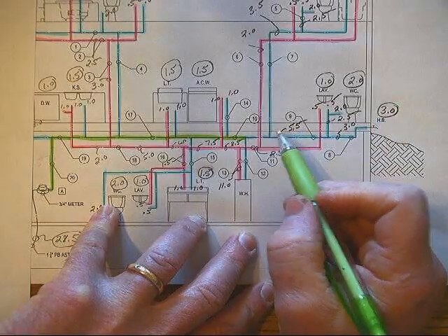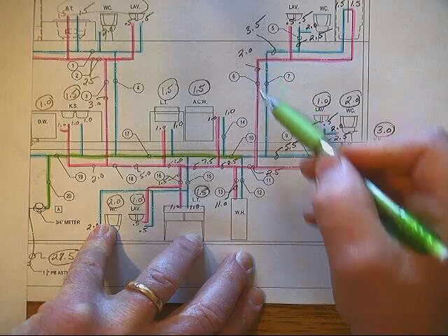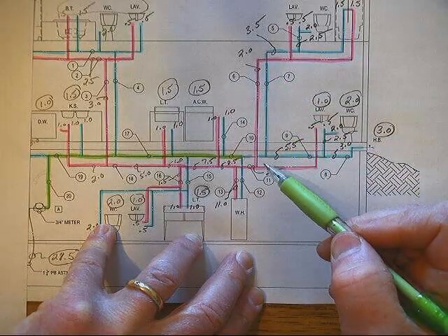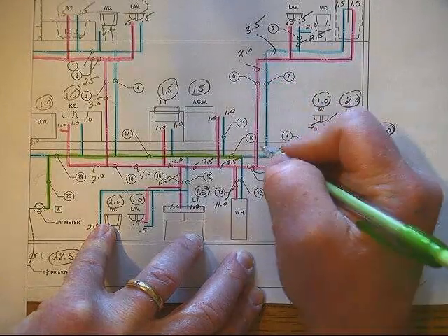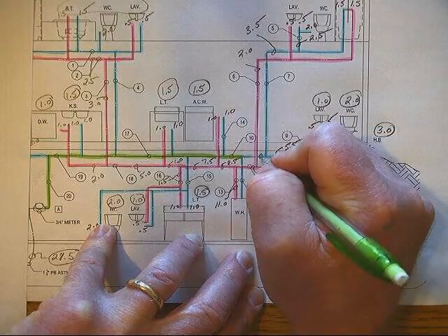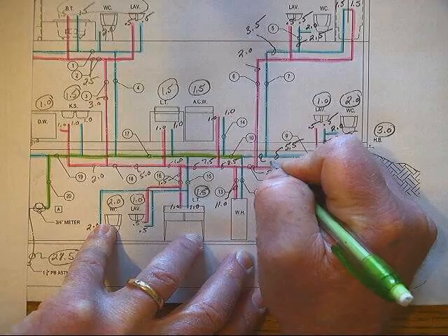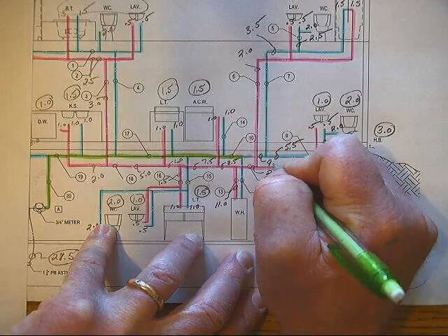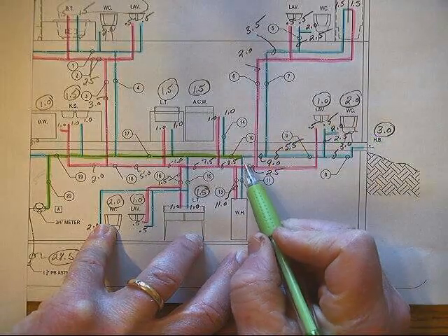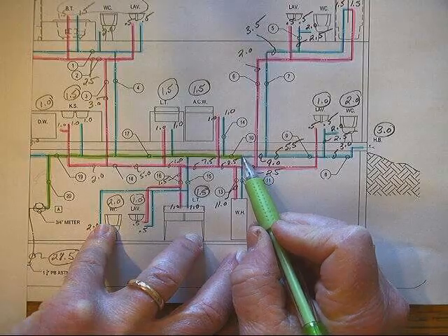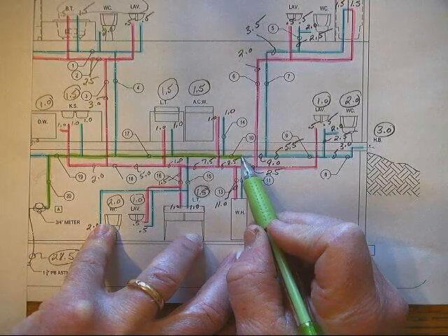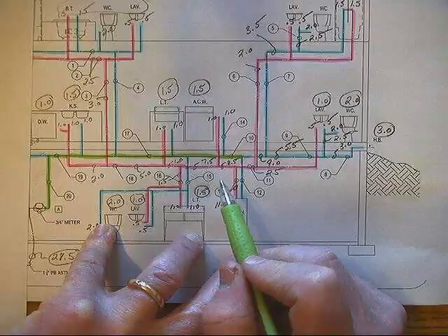That 5.5 would tie in with the 3.5 that's coming down, and this section of pipe right here, right before the water heater T, would be loaded to 9 WSFU. As you can see, that piece of pipe touches the cold main, and at that point we would stop adding.